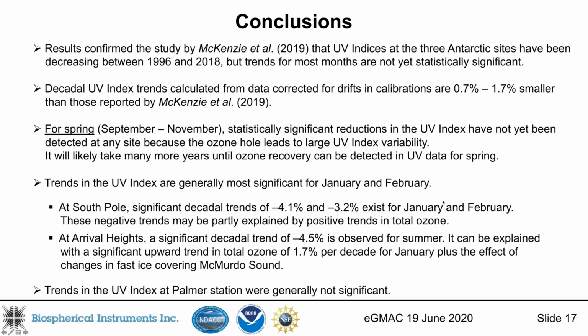Well, it's always a struggle in making sure that the calibration standards you have are consistent. The standards you get from NIST have an uncertainty of 1% at the time it leaves the facility, but they don't guarantee what that uncertainty will be at the time it's at your doorstep. And that's only one uncertainty that contributes to UV measurements. So I believe we just have to keep comparing lamps and keep good records of lamps, and don't use lamps for a long time, and compare new lamps back to those lamps to ensure that we have stability in calibrations.